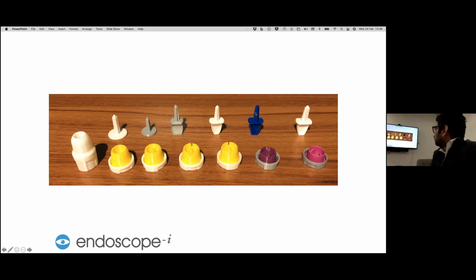But the other development here, hopefully you can see between the white and the blue, is that we wanted to make a slightly bigger cut in the mask, because what we were finding was we actually matched this diameter to the largest endoscope, but we realized that the cut needed to be slightly bigger because it was creating a rim of mask that was uncut, that meant that some of the fatter scopes were struggling to get through. So they would get through the valve. We couldn't understand when we were passing it through the valve, the scope was going through no problem, but when we put it in the mask, it was getting stuck, and it was actually because the mask wasn't cut wide enough. So that's the reason why we went for this slightly wider approach, and hence these are the final versions here.